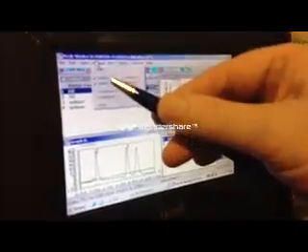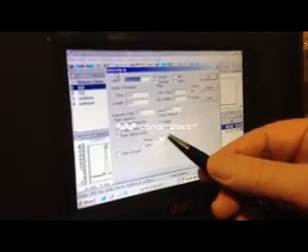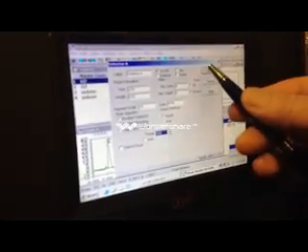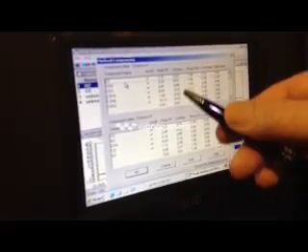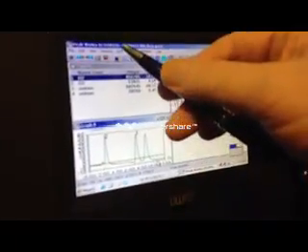We can also go in and look at the detectors. These are the parameters that you use for integration. This is the range, so the range can change. This is what we use for the components, so you put the components in here. Here's the retention time, and these are the windows. You can set the windows, usually five seconds on either side. You can also put response factors in here for detector A and detector B. And for standards, you can run up to four standards for each one of the components.